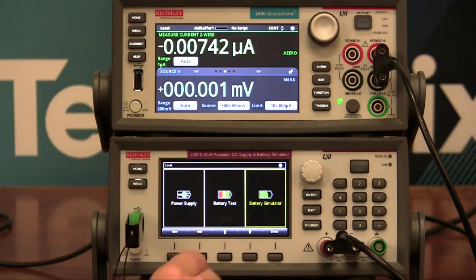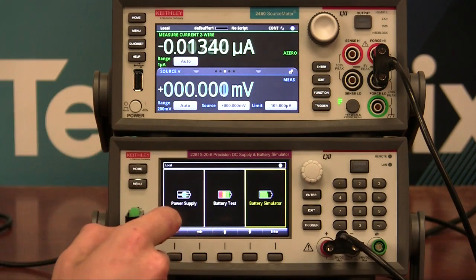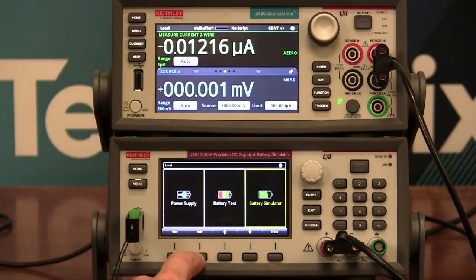The first step is to load a AA battery profile into the 2281. So I've got a profile loaded onto this flash drive, and I'm going to import it into this battery simulator.